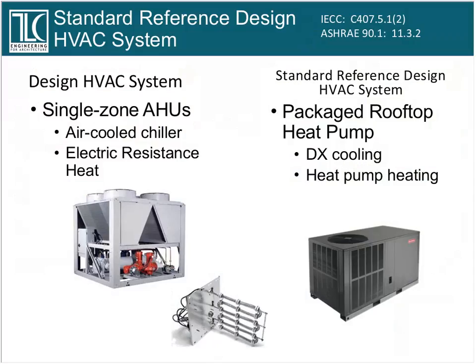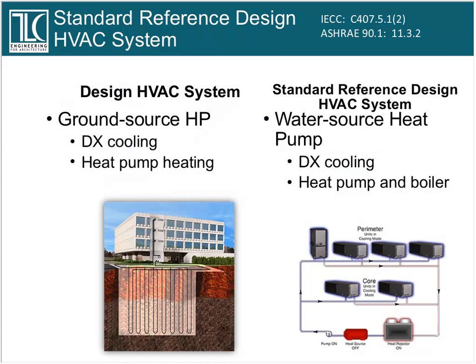And it's interesting to note that the modeling rules make you make some really interesting choices. So if you design your HVAC system to be packaged single zone equipment with electric resistance heat, you're going to be competing against a packaged heat pump system, which uses less energy than electric resistance heat. So you have to take that into account when you do your design. Your design might be for a ground source heat pump system. When you compete against that, you actually compete against a water source heat pump system that uses some sort of cooling tower to reject the heat rather than the earth does.